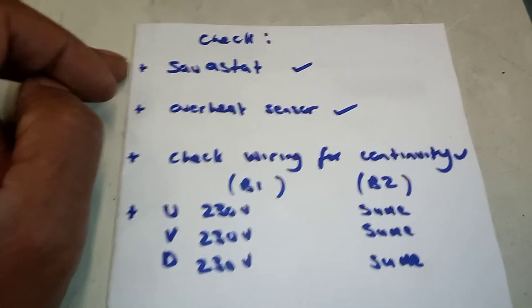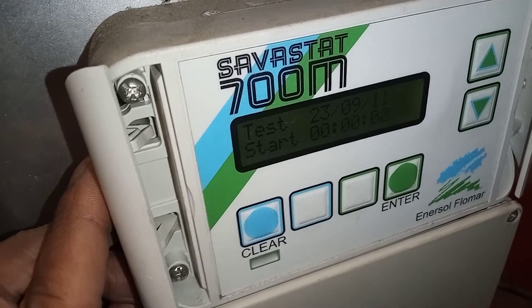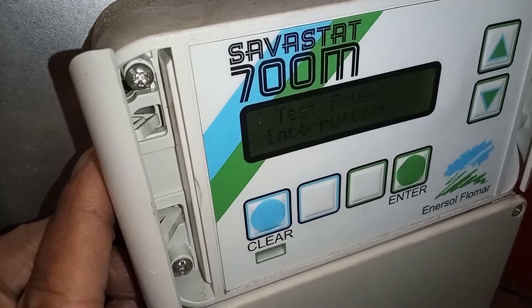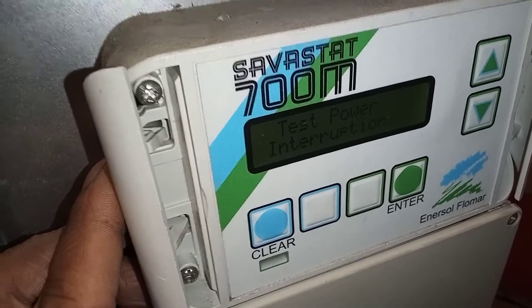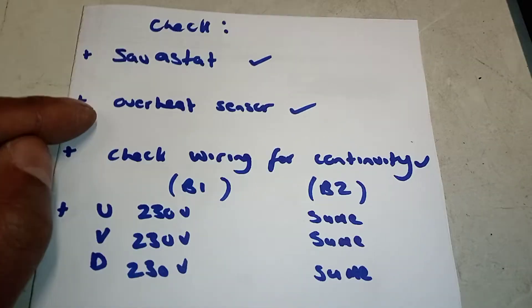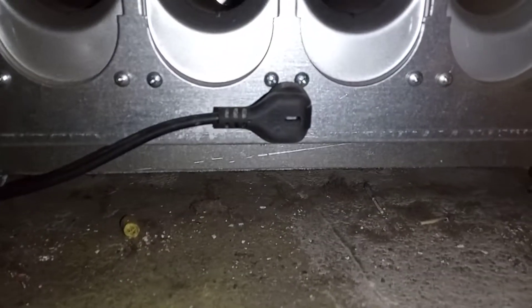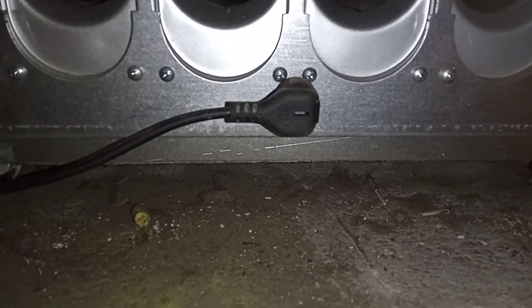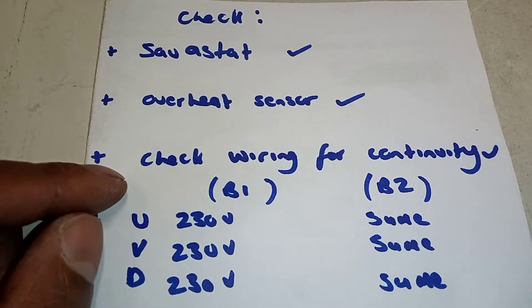First I went to the Savastat at the back of the boiler to make sure that there were no problems and that it wasn't holding the boilers off — that was fine. Then I went to the next thing: the overheat thermostat — the overheat sensor. I went down and double-checked that, and that was fine too.